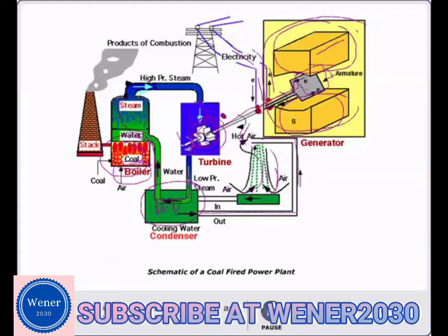That is the reason this turbine part is notoriously inefficient, and the boiler part is pretty good actually. It's about 90% efficient. This is about 40% efficient. But once we turn this thermal energy into mechanical energy, conversion into electrical energy is pretty efficient. This generator is almost 95% efficient.